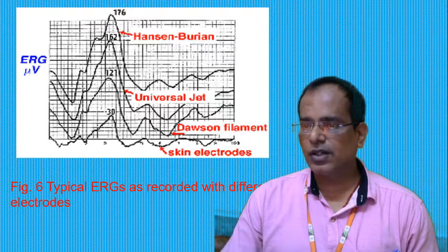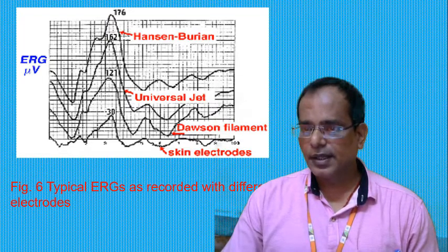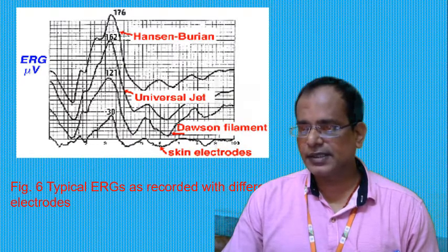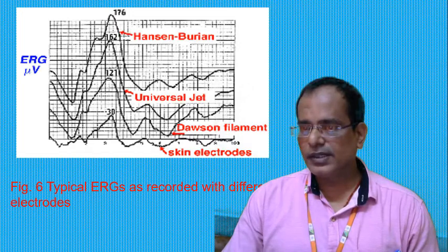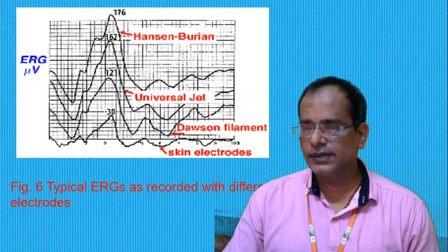If the electrodes are to be reused, they should be sterilized with a solution that neutralizes prion-transmitted disease such as Creutzfeldt-Jakob disease, called CJD. Follow the sterilization recommended by the manufacturer. We can also use household clothing bleach, whose active ingredient is sodium hypochlorite, diluted to a 10% solution with distilled water.